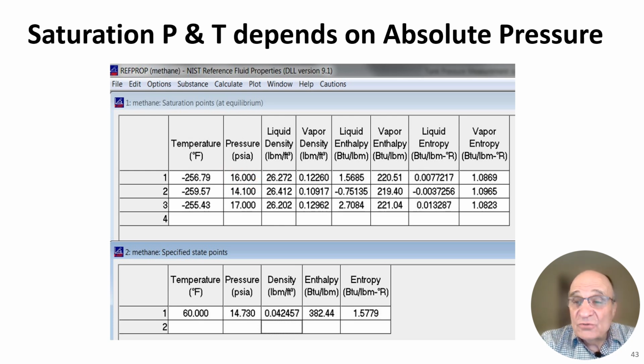And whenever you're dealing with thermodynamic software, you deal with absolute pressure because that's the scale it's designed to operate at. Now you can use gauge pressure, but you have to put in a correction factor to tell it what your barometer is. But if you go with absolute pressure, it can tell you right away what your saturated temperature is associated with that absolute pressure. It could also tell you what your liquid density is, what your vapor density is, what your liquid enthalpy is, vapor enthalpy, liquid entropy, vapor entropy, and many, many more properties of that fluid, depending upon which ones you selected to populate or investigate. In this case, I selected only density, enthalpy, entropy, and temperature.